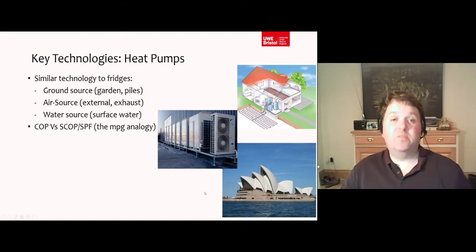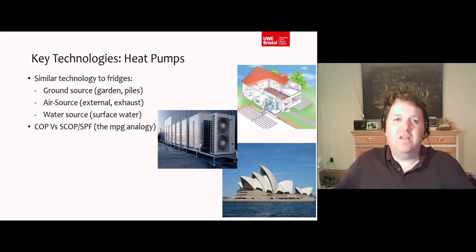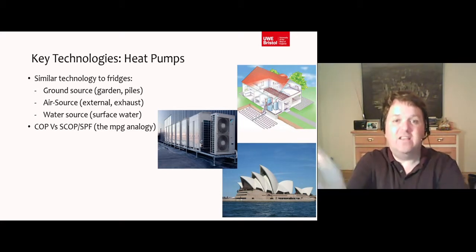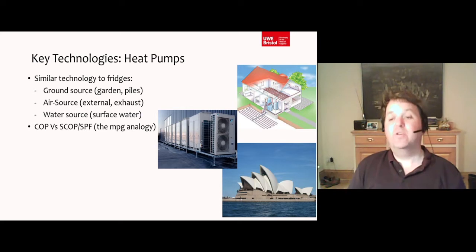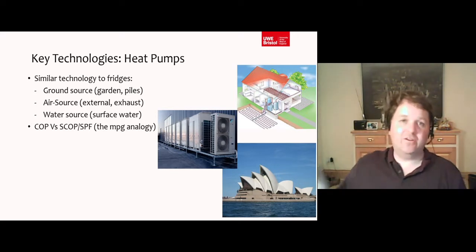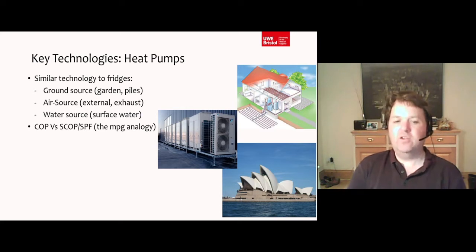The efficiency of a heat pump is measured by something called the COP — the coefficient of performance. When you buy a piece of kit, they'll tell you this air source heat pump will have a COP of 3.5, which means for every unit of electrical energy the compressor consumes from the grid, it'll deliver 3.5 units of heat. Electricity is high-grade energy and heat is low-grade energy, so there's an entropy change. By using a heat pump you're getting a one-to-three ratio, so you're getting much more heat for the energy you're using, compared to a bar heater which gives you only a one-to-one ratio.